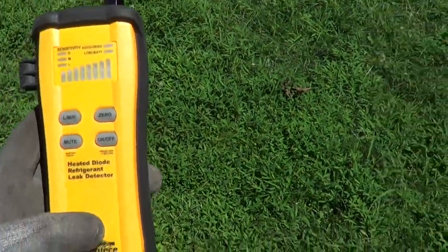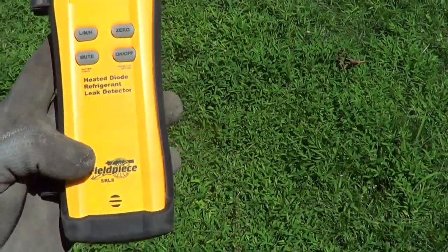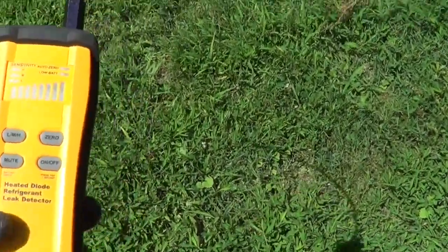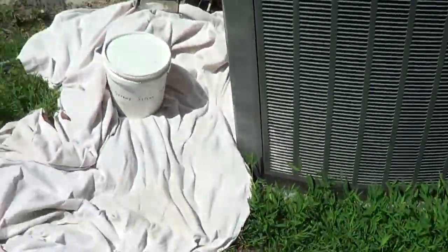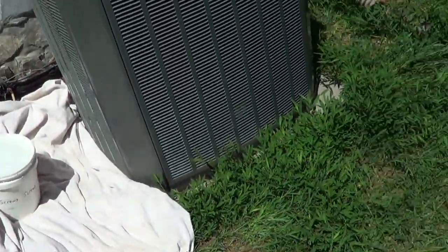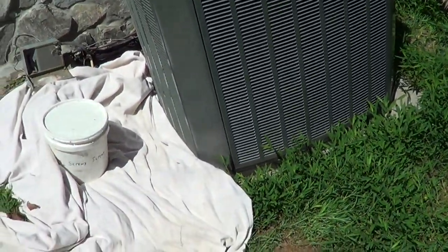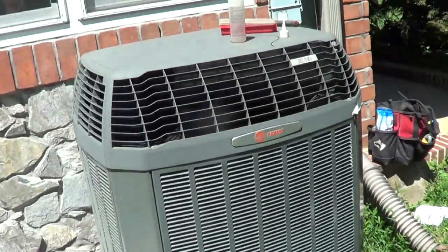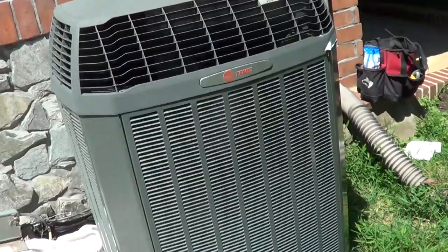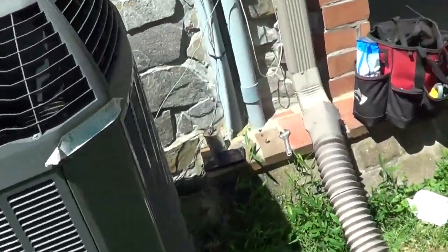So you might be laughing that the SRL-8 is a useless piece of junk, but it's very good at getting small leaks. I was suspicious this system was low on refrigerant, and then the hits I was getting everywhere were telling me it was a very large leak.